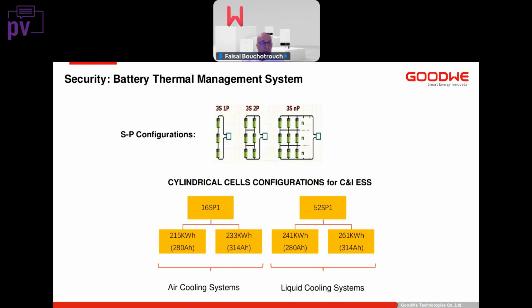As we grow in capacity and power, thermal management becomes key for this kind of system, so the industry is adopting the following barrier as a reference for the cooling system: air cooling for capacities below 233 kilowatt hours, and liquid cooling for capacities above 241 kilowatt hours. This depends on the manufacturer, but it's a key reference.